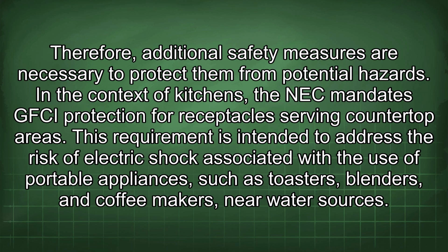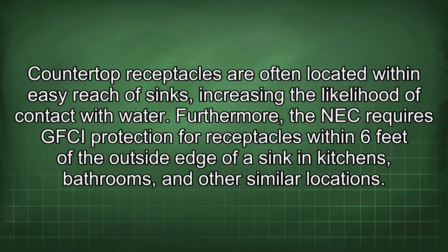In the context of kitchens, the NEC mandates GFCI protection for receptacles serving countertop areas. This requirement is intended to address the risk of electric shock associated with the use of portable appliances such as toasters, blenders, and coffee makers near water sources. Countertop receptacles are often located within easy reach of sinks, increasing the likelihood of contact with water.